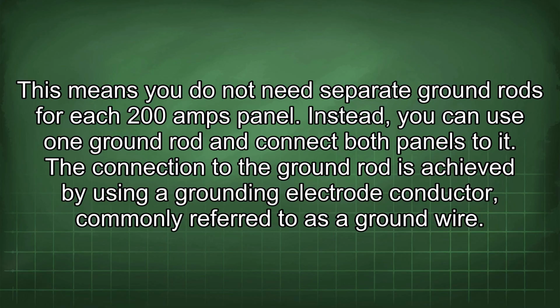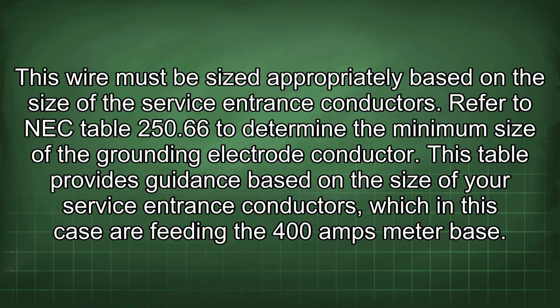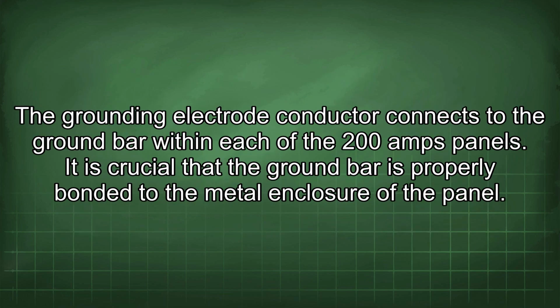The connection to the ground rod is achieved by using a grounding electrode conductor, commonly referred to as a ground wire. This wire must be sized appropriately based on the size of the service entrance conductors. Refer to NEC Table 250.66 to determine the minimum size of the grounding electrode conductor. This table provides guidance based on the size of your service entrance conductors, which in this case are feeding the 400 amp meter base. The grounding electrode conductor connects to the ground bar within each of the 200 amp panels.